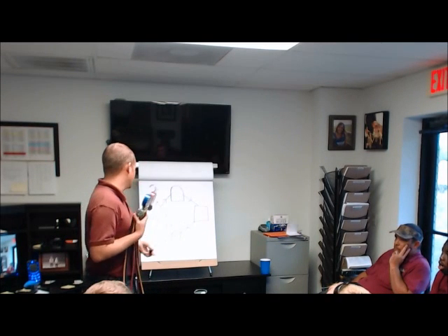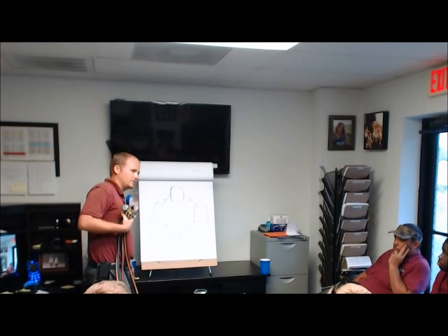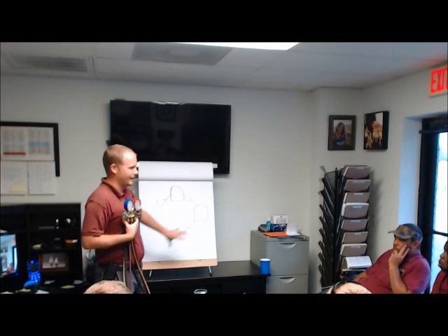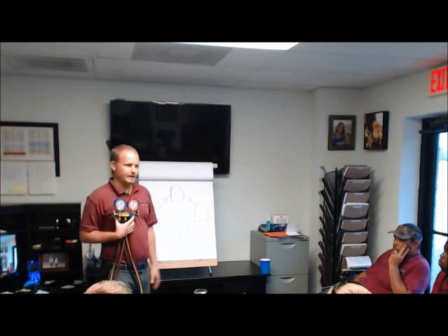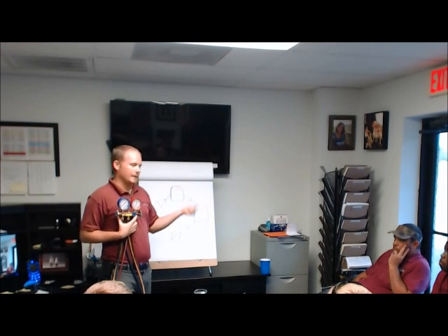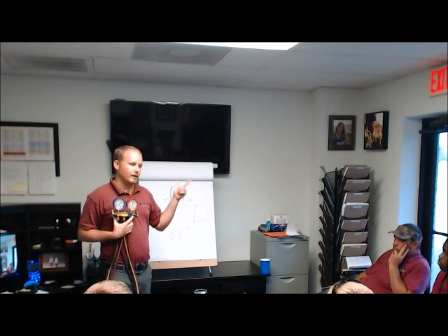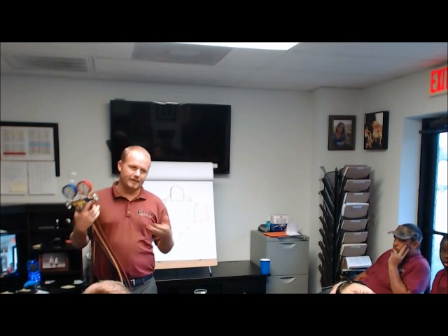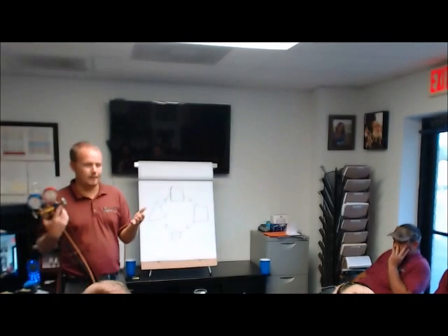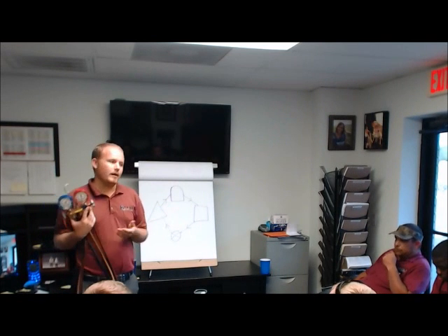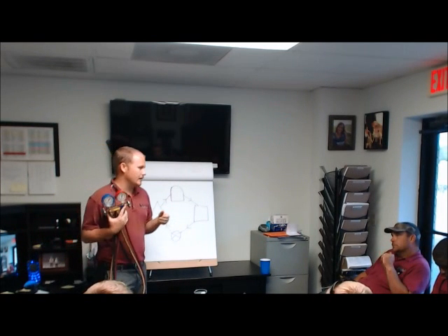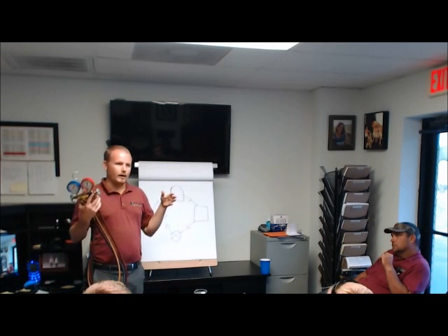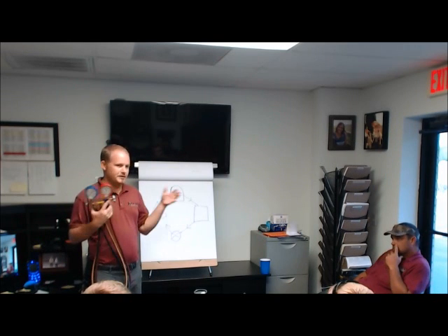So when we're talking about a refrigeration circuit, we're talking about a closed system, meaning that the refrigerant is completely encapsulated inside this system. Depending on the type of refrigerant, the temperature conditions, and the pressure, all those things affect one another. Whenever you have an increase of temperature in a closed vessel, you also have an increase of pressure in that vessel.